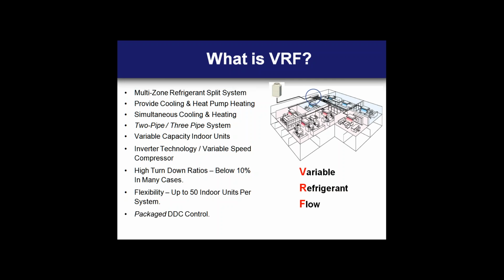You'll hear terms such as 2-pipe versus 3-pipe. This really comes down to the distinction between the Mitsubishi heat recovery system and the majority of other manufacturers' heat recovery systems. Mitsubishi uses a 2-pipe variation. Other manufacturers actually use 3 pipes, but they're essentially accomplishing the same process, and we'll talk about that later as well.